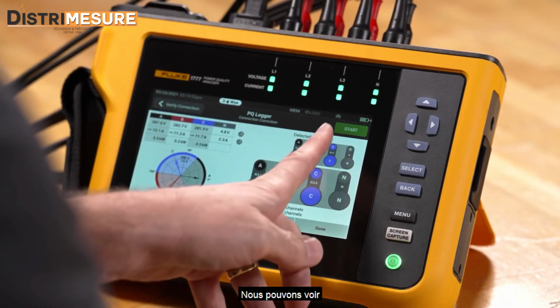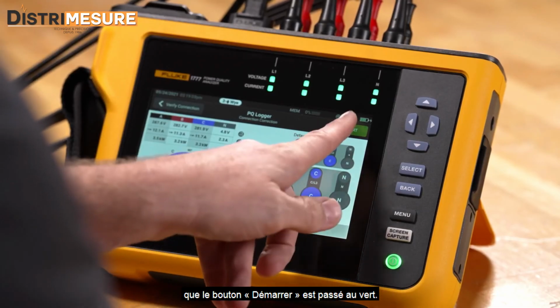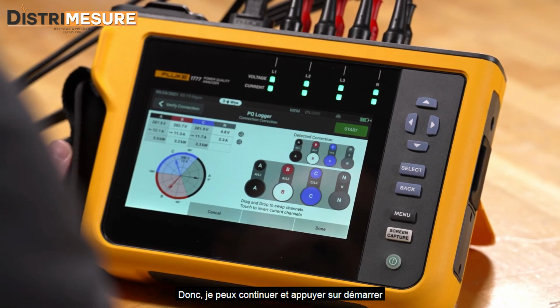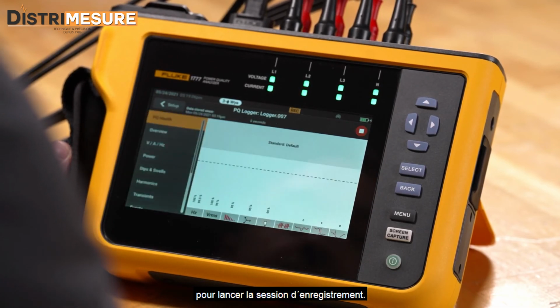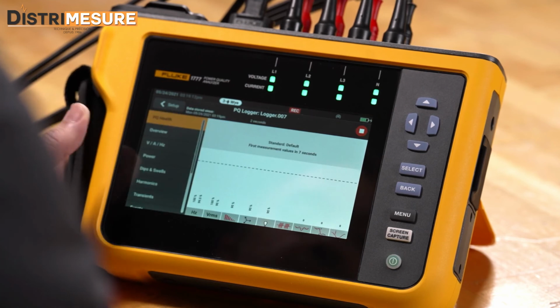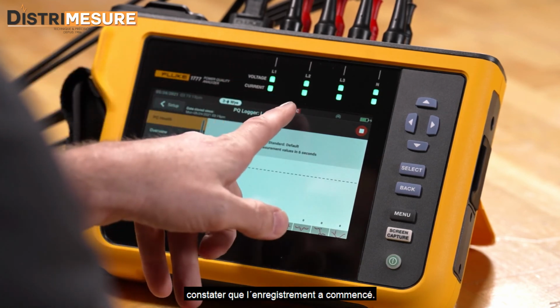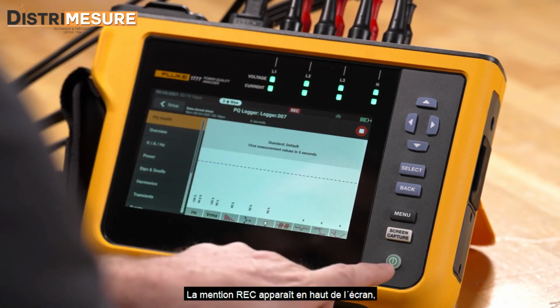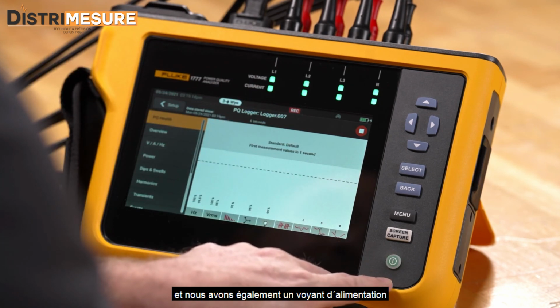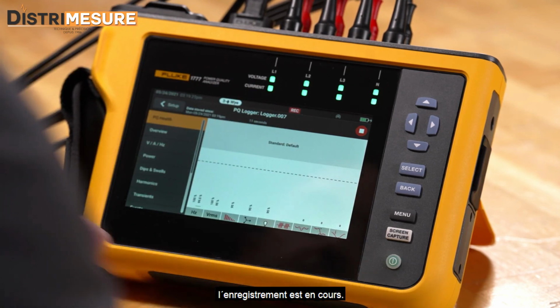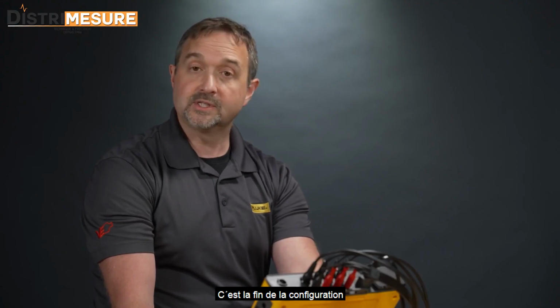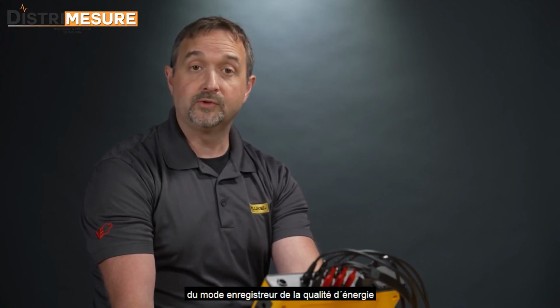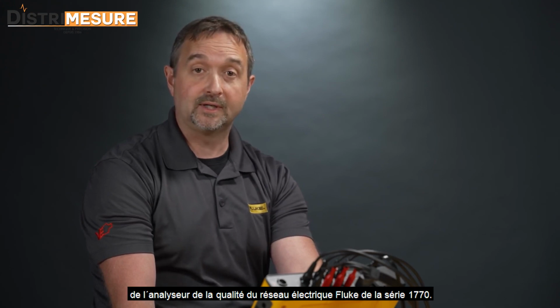Now we'll see that we have start as green, so I can tap start here to initiate the recording session. Right now we'll see that this recording is started. We have REC at the top of the screen, and we also have a flashing green power indicator indicating that the recording is indeed in progress. And this concludes the setup of the PQ logger mode for the Fluke 1770 series power quality analyzer.